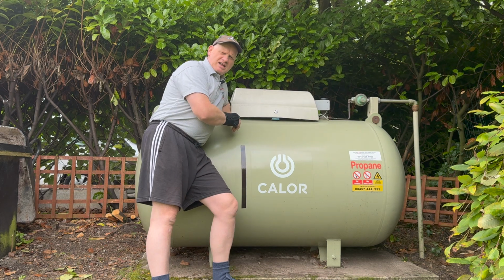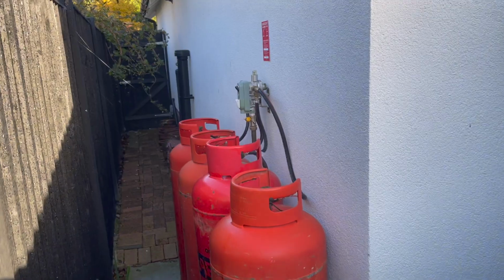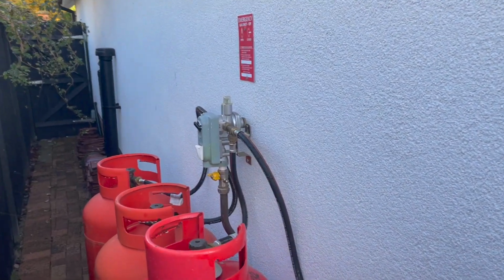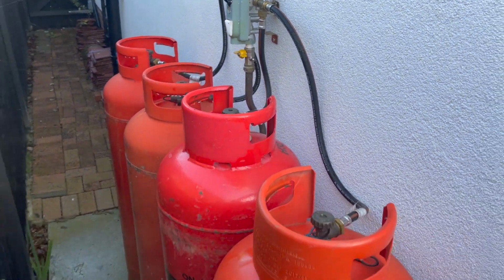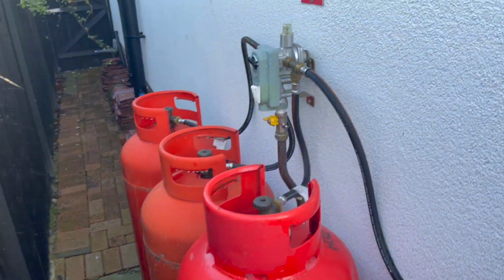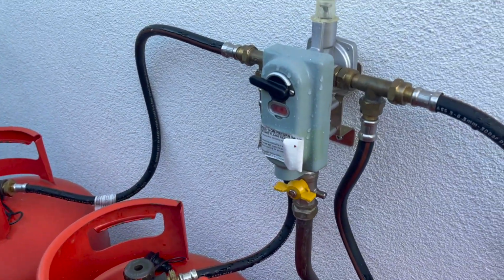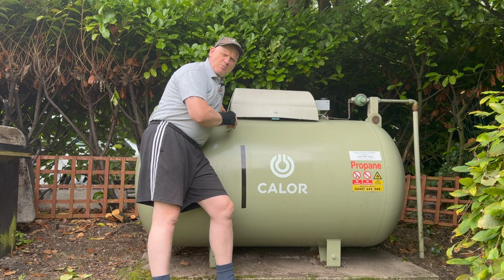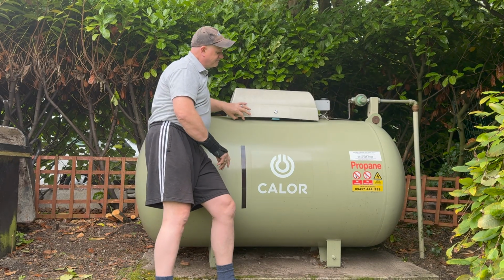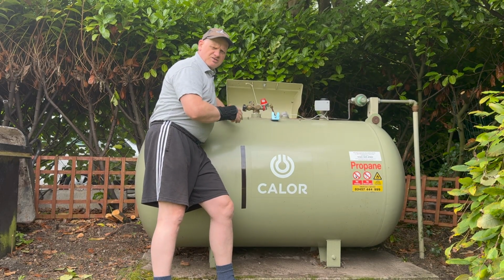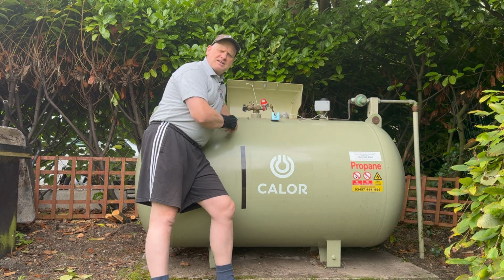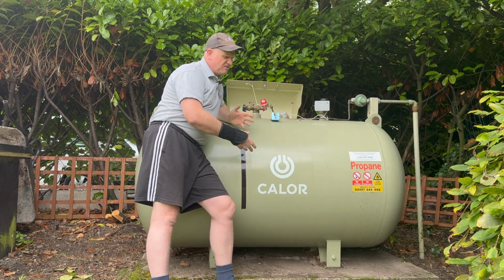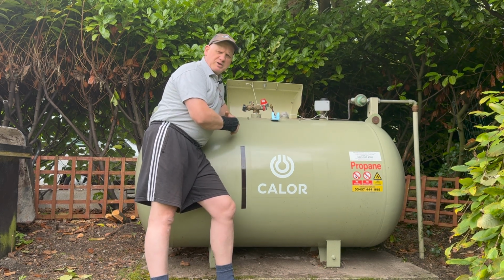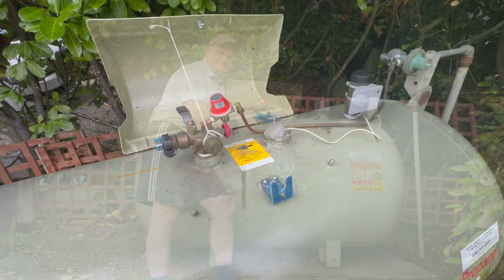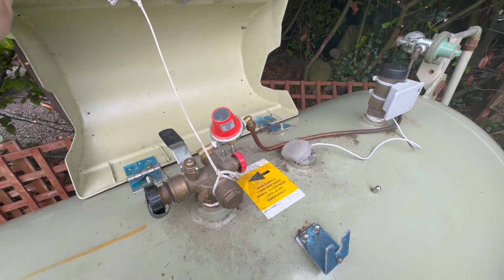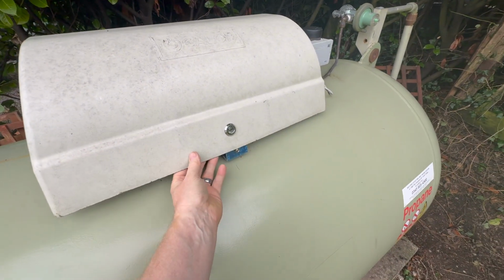Now the first thing I like to do is check whether the cylinders or the gas storage tank has actually been installed correctly and is to regulations. So let's find out exactly if this cylinder is installed correctly and how we're going to do this procedure for servicing an LPG combi boiler. So everything seems okay with this LPG tank.